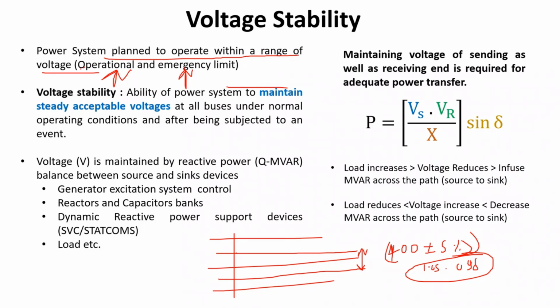The various operational limits for each voltage level have been defined in the CEA standard as well as the Indian Electricity Grid Code. We will look into that in a later slide. But in general, for 400 kV and 765 kV, it is generally plus minus 5%, while the 220 kV system, if you see, it is plus minus 10%. So that's the operational limit.